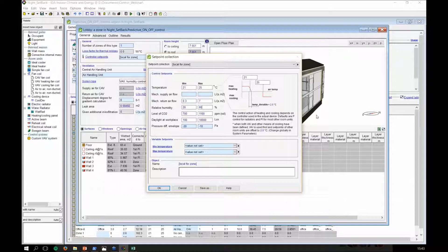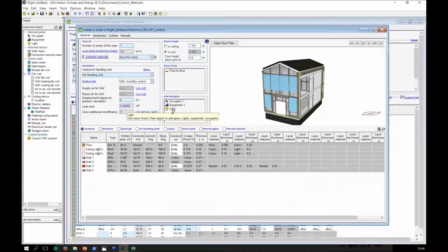This answers me a bit, yes. Now we have a very special topic that we work on: a swimming hall. We have humidity coming out from the water, then humidity from the occupants as well, raising the relative humidity indoors. Our goal is to measure the humidity indoors and then give an appropriate control to the air handling unit to change two things. Firstly, the cooling temperature to get dehumidification, so drying the air, and secondly, the control of the air volume, how much airflow we want to increase or decrease. So this is in my imagination how we should go on.